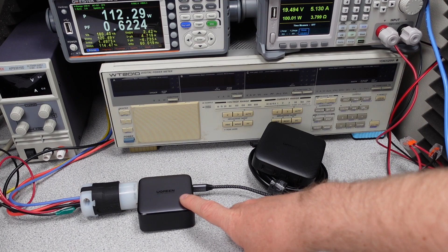Let's go ahead and take this one up to overload and see where we get. 105 watts, 106 watts, 107 watts, 108 watts, and it's off. So it looks like this device can do about 108 watts before it trips out the overload. I feel it's starting to get a little warm, and that's okay - that's really an acceptable number, not a problem at all.